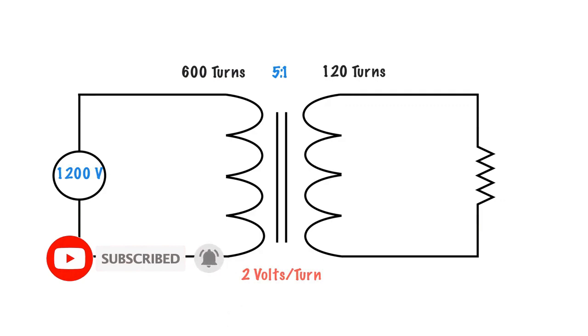Now you see here that I've got 1200 volts and I have 600 turns. That means that if I go 1200 divided by 600, I have 2 volts per turn. For every turn in the primary winding, I have 2 volts. Now, the nice thing with transformers is whatever my volts per turn are on my primary side will also be the volts per turn on the secondary side because they're sharing the same magnetic circuit.